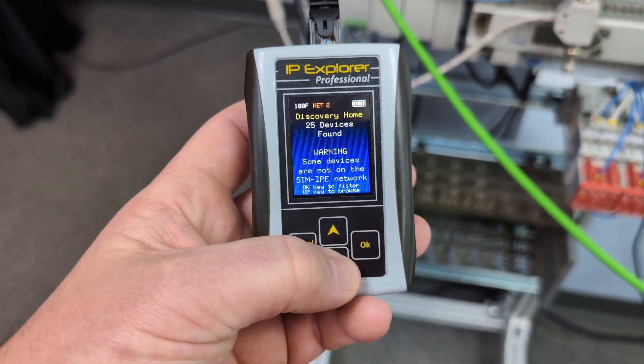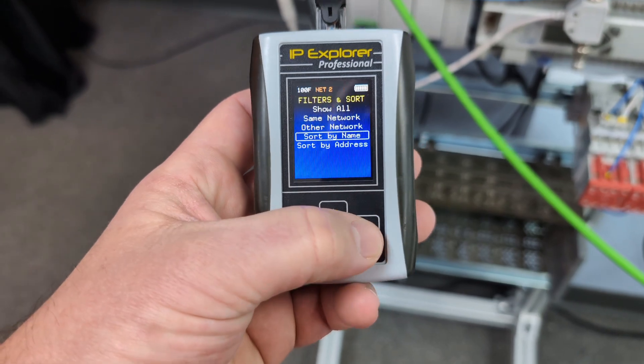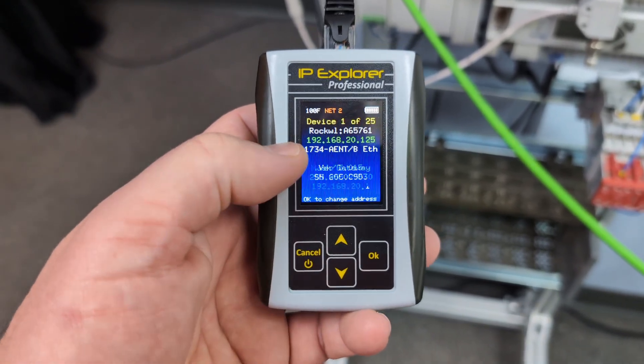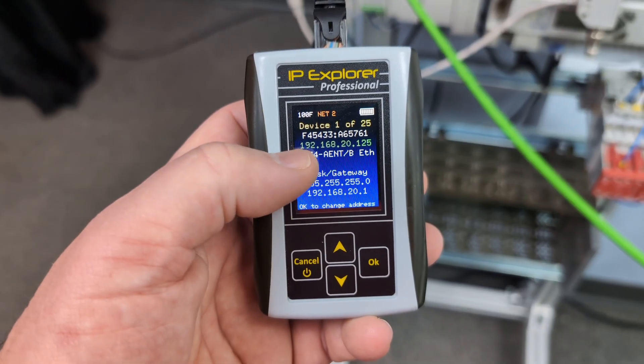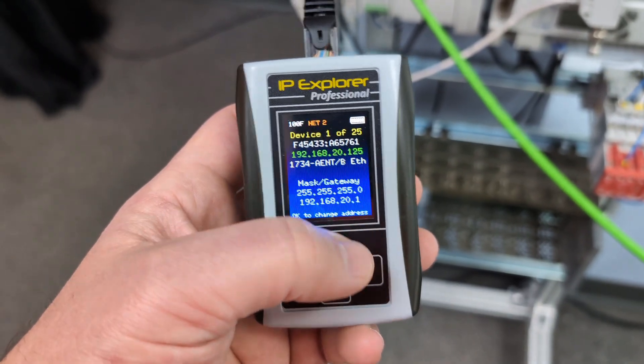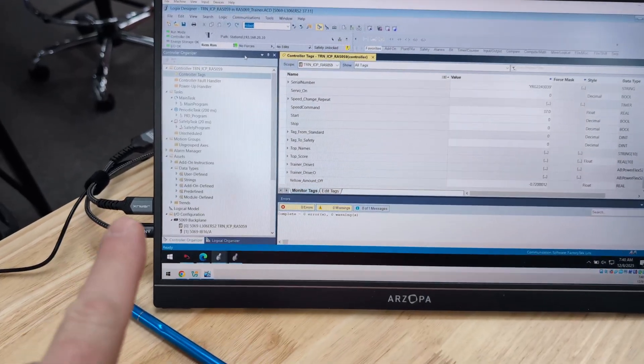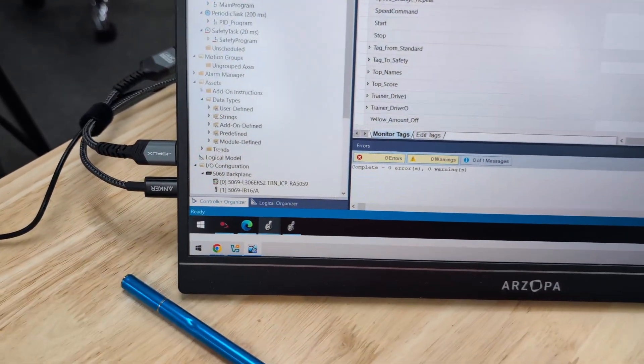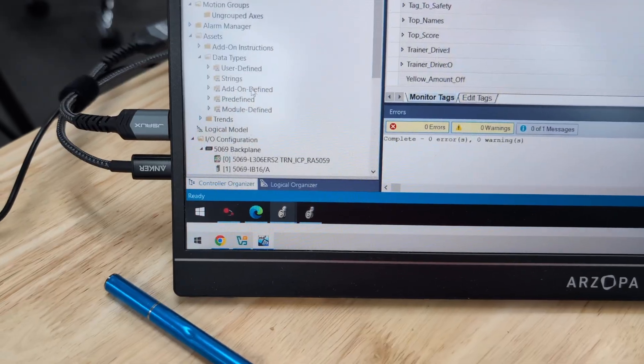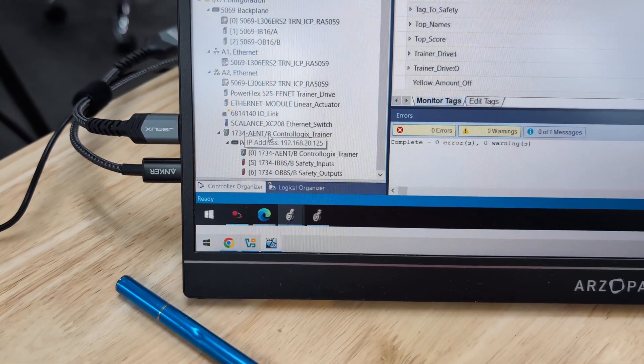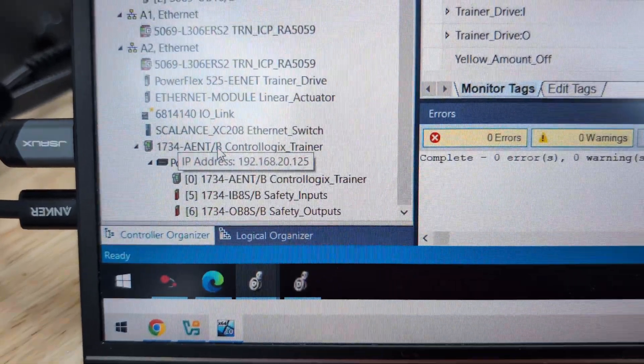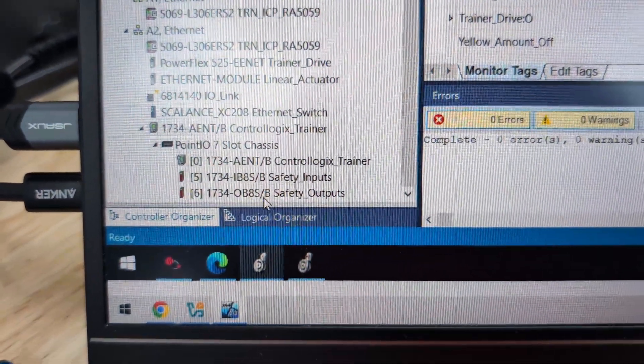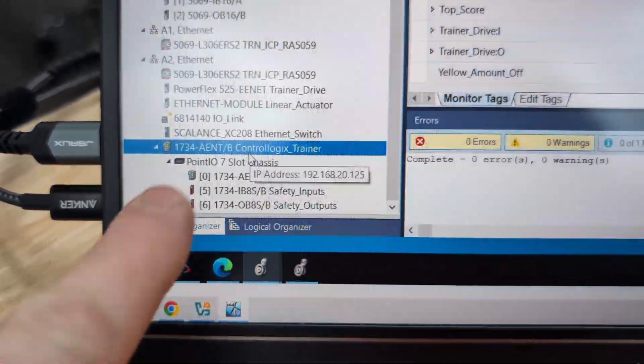And maybe it's written down. That's another one people tell me it's usually written down on them. I've worked on thousands of machines. The IP is almost never written down. But we could go up there. And we're going to sort by name. The 1734-AENT/B is 192.168.20.125.